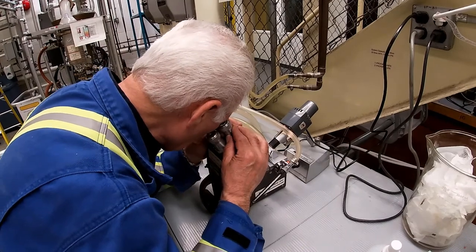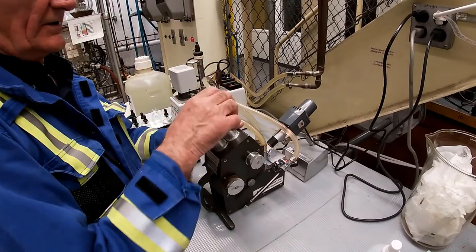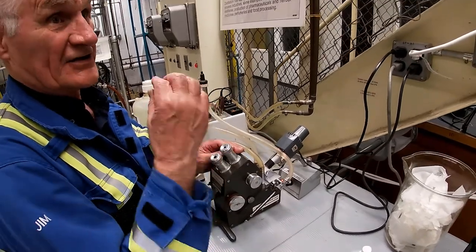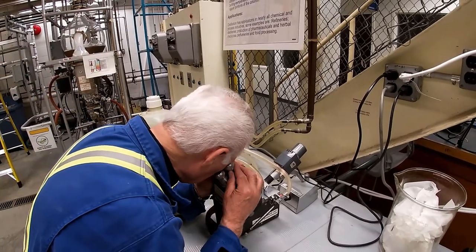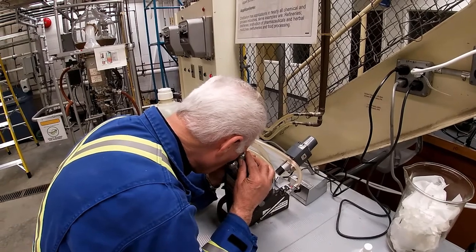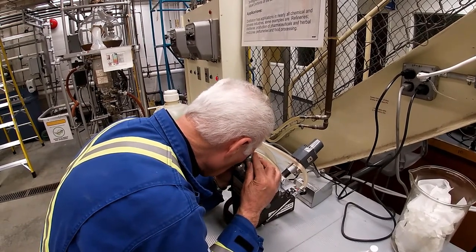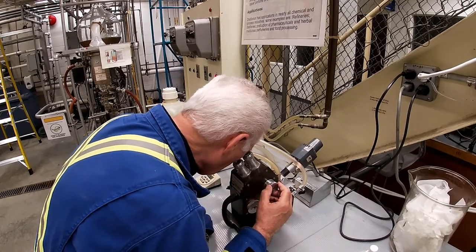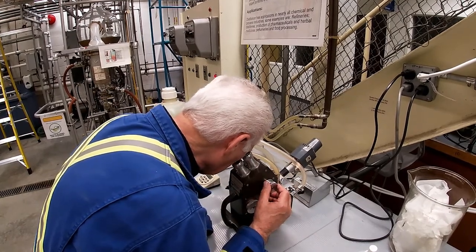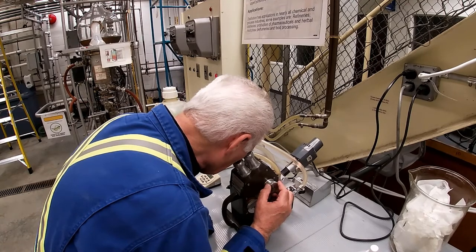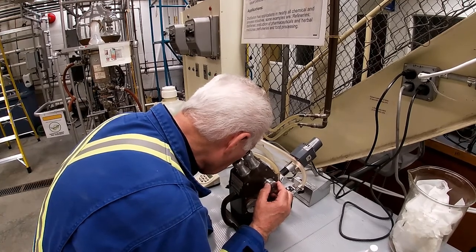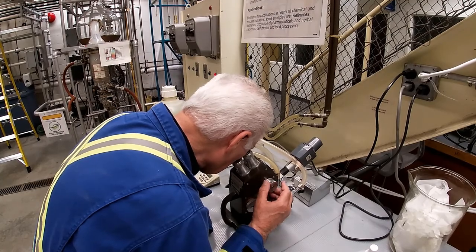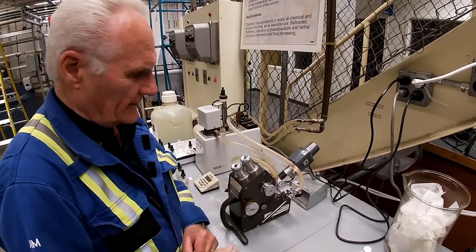First of all, the focus isn't quite right. You got to watch it. This is a knurled handle on here, and you think you can twist it and adjust it, but you can't. It just slides up and down. So you get the crosshairs still there, absolutely clear. And I'm adjusting right now for blue, and adjusting the other way to red. And come back and find that sweet line that it's just a black line across there.